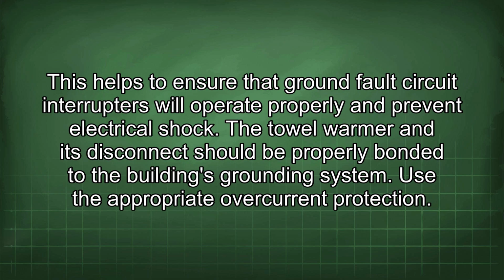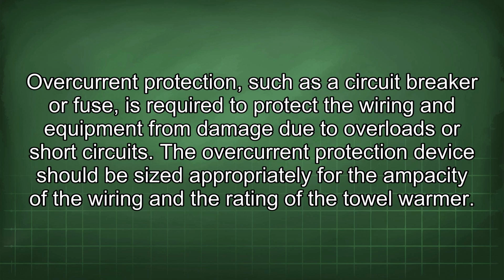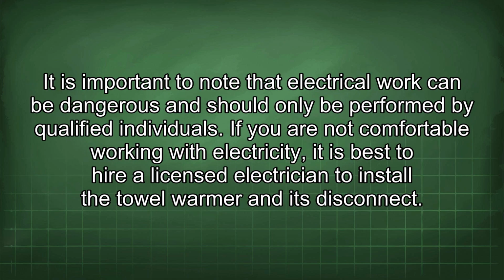Use the appropriate overcurrent protection. Overcurrent protection, such as a circuit breaker or fuse, is required to protect the wiring and equipment from damage due to overloads or short circuits. The overcurrent protection device should be sized appropriately for the ampacity of the wiring and the rating of the towel warmer. It is important to note that electrical work can be dangerous and should only be performed by qualified individuals. If you are not comfortable working with electricity, it is best to hire a licensed electrician to install the towel warmer and its disconnect.